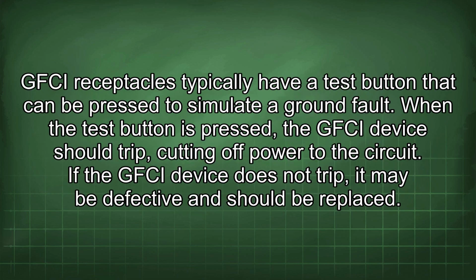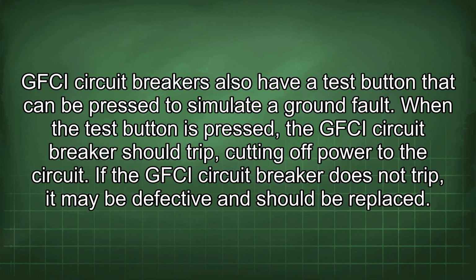properly. GFCI receptacles typically have a test button that can be pressed to simulate a ground fault. When the test button is pressed, the GFCI device should trip, cutting off power to the circuit. If the GFCI device does not trip, it may be defective and should be replaced. GFCI circuit breakers also have a test button that can be pressed to simulate a ground fault. When the test button is pressed, the GFCI circuit breaker should trip, cutting off power to the circuit. If the GFCI circuit breaker does not trip, it may be defective and should be replaced.